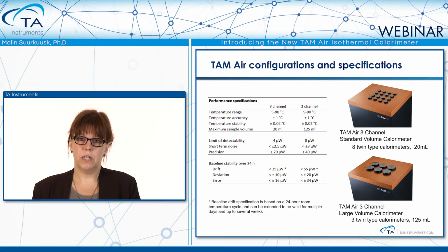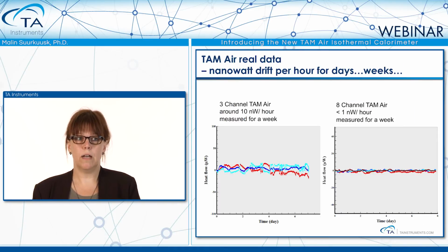This specification doesn't mean that the temperature is constantly drifting every 24 hours. It's more that it's based on the 24-hour cycle of a room temperature variation. And the baseline stability is actually much better than you see on this specification, because if you elongate the time, you will see that the baseline stability is essentially 0, which can be seen in the next example with the data of TAM Air, real data that's been measured for several days, and we can see that the drift is nanowatt per hour, and that's measured for several days or up to a week. So we have nanowatt drift per hour or day, even if you can see some fluctuations within a 24-hour cycle.